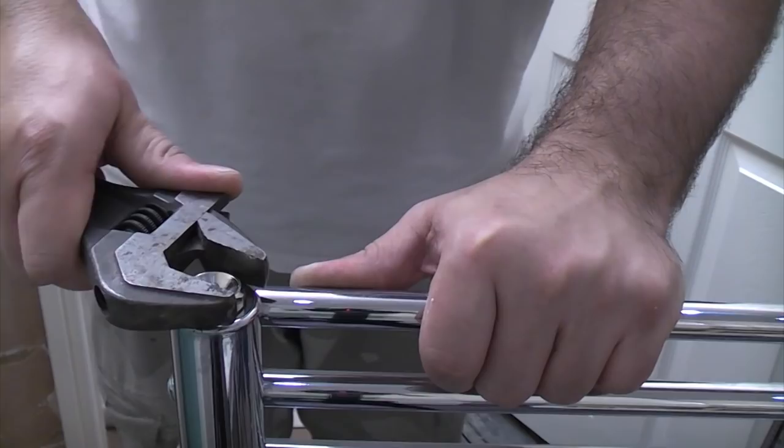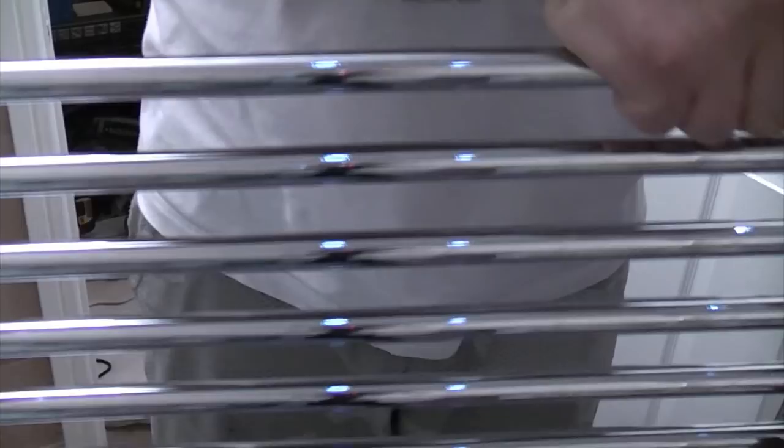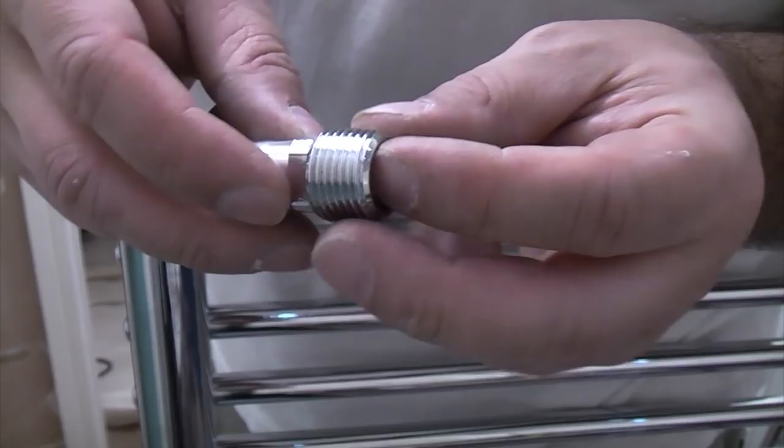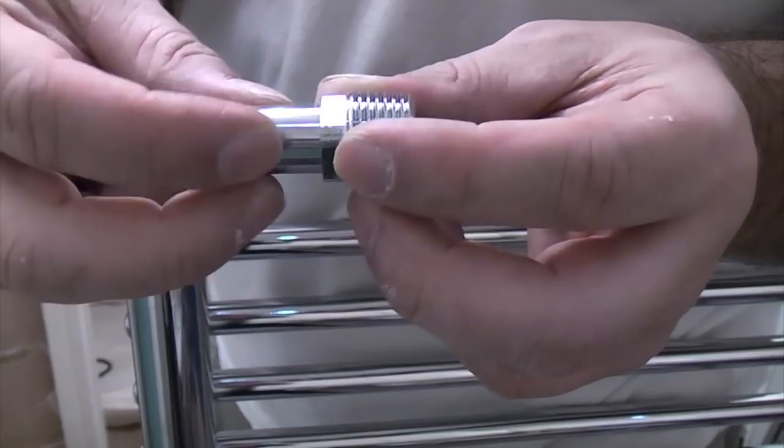So once you've done that you can then turn the radiator over. Now in this end goes radiator tails and often you get these on radiators and you actually need a radiator key which is a large allen key to insert them but this particular one has got flats on it so we can quite easily put those in just using a spanner.